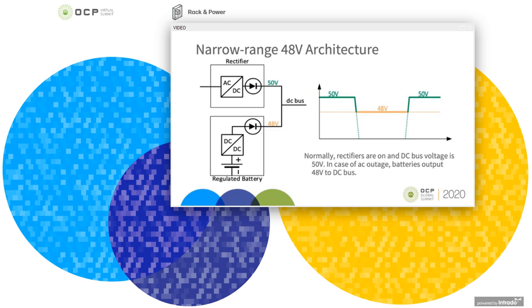In this approach, we basically regulate the rectifier to 50 volt fixed and the battery to 48 volt fixed. There are two ORing ideal diodes, ORing FETs, in the design as well. So basically, when the AC voltage is available, the voltage on the bus is 50 volt, and when the AC is out or there's a rectifier failure, it actually goes to the battery with the 48 volt output.